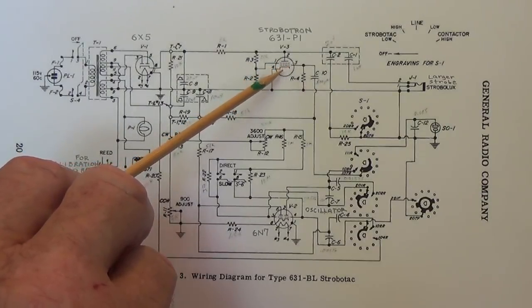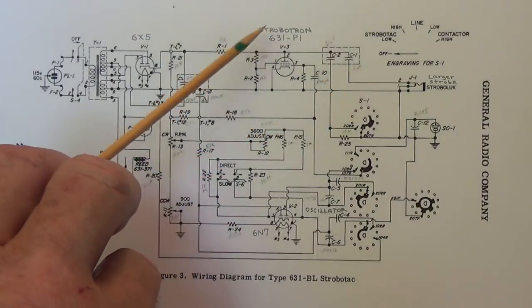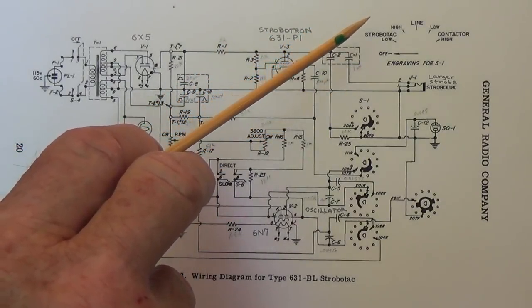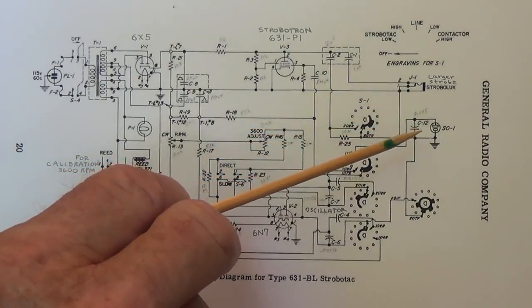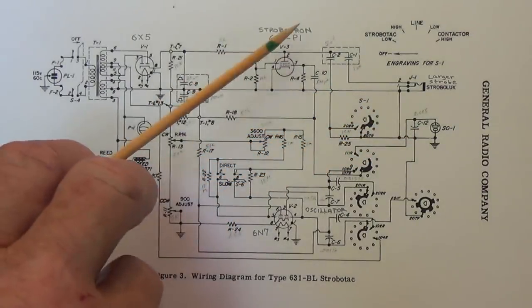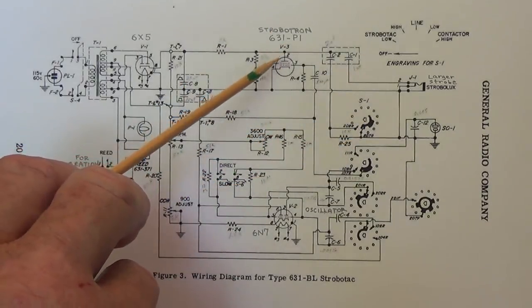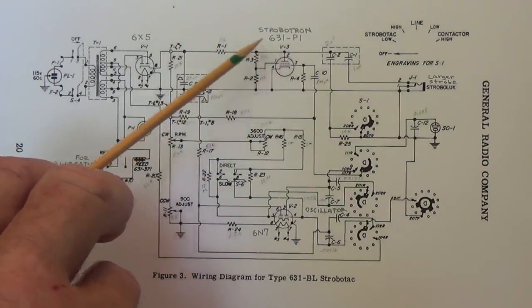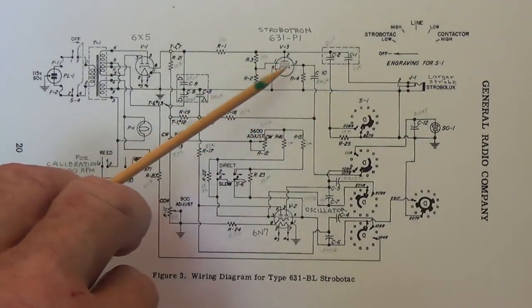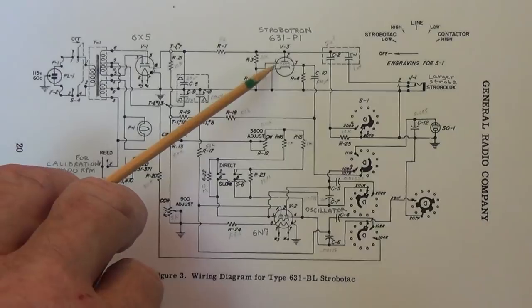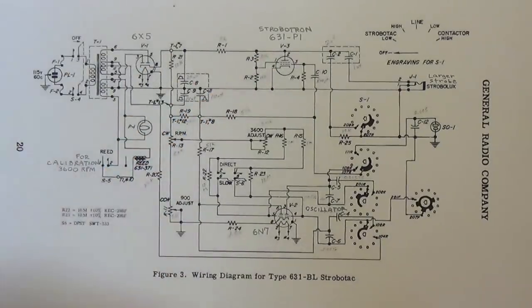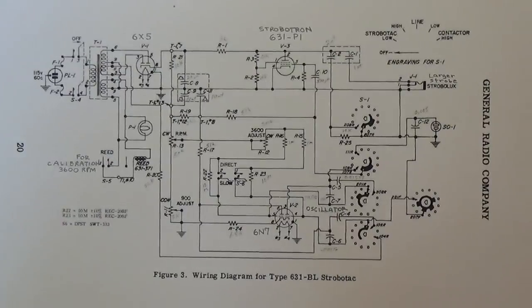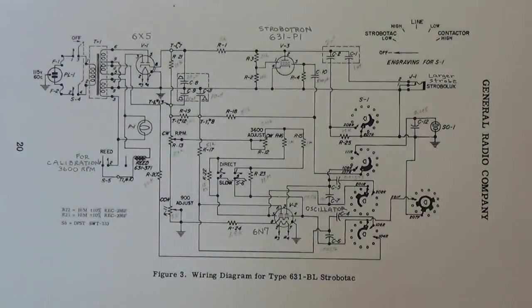You have to have a very special light source when you're going to strobe, because with an incandescent light, if you were to apply power to it and then take power away, there would be a glow up until full brightness and then a glow as the brightness diminishes, which wouldn't give you that sharp, clear-cut strobing that you want. So this Strobotac apparently is able to flash on and flash off instantaneously, as fast as 14,400 times per minute. That makes it a very special tube indeed. I think other, more modern devices would use a neon bulb of some sort for this purpose.